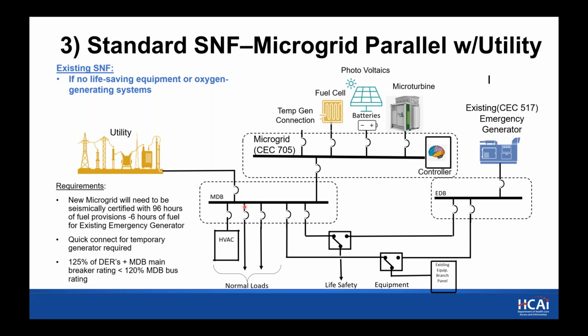So let's look at the requirements. The new microgrid will need to be seismically certified. It'll need to have 96 hours of fuel provisions with 6 hours minimal on site. In this case, the existing generator would only need to have 6 hours. And someone might ask, why? Is this the one case where it only has 6 hours? Well, the entire facility is being backed up for 96 hours. So the emergency system, the life safety system, everything is backed up for 96 hours. And that's being done by this microgrid. And so you would not need to supplement the fuel for the existing emergency generator. Another requirement, and I showed here, is a quick connect for a temporary generator is required.